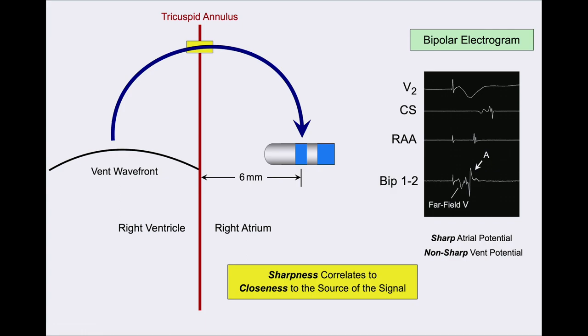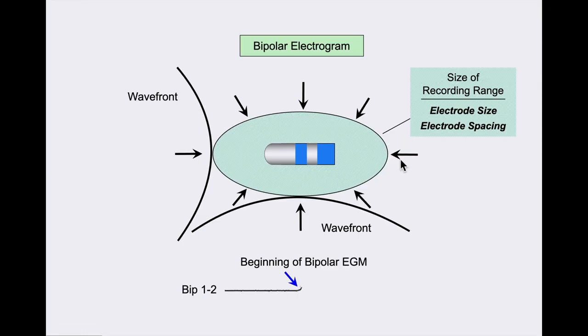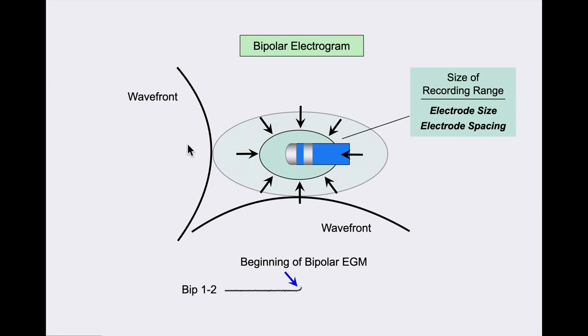To summarize, the sharpness of the signal correlates to how close the source is to the electrode. The size of the recording range depends on both the size of the electrodes and, to an even greater extent, the inter-electrode spacing. If we decrease the size of the electrodes and bring them closer together, the recording area gets much smaller. As the wavefront crosses in a shorter distance, the electrogram gets narrower, sharper, and actually a little bit larger.